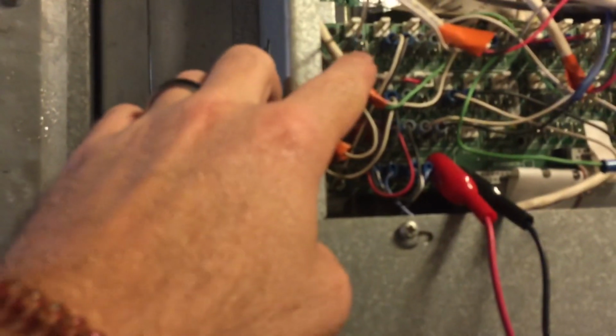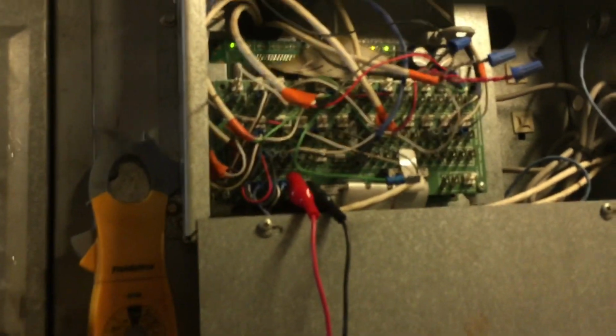So it's controlled from this MP580 Trane controller up here, and it is analog output number 1. I started checking to see that the output didn't go bad, or it's not getting dragged down when it's hooked to the device. But what I noticed was when I opened this top power panel, I noticed that there is 2 transformers there. Here is 2 separate power supplies going to different devices, 2 different setups.